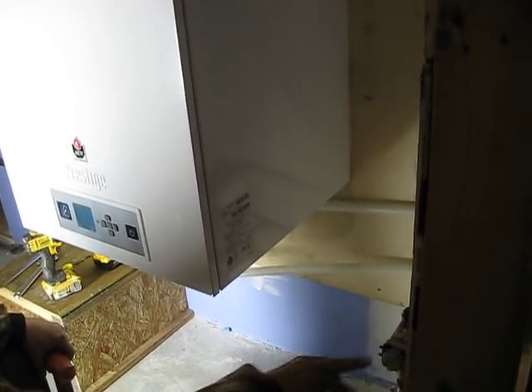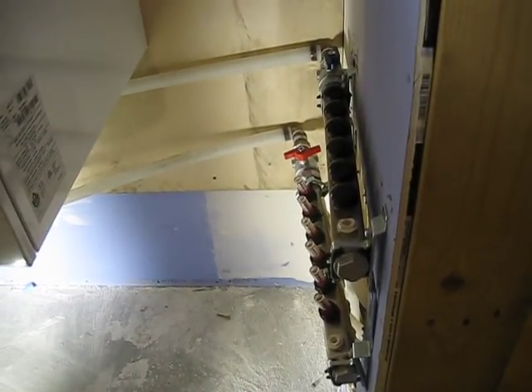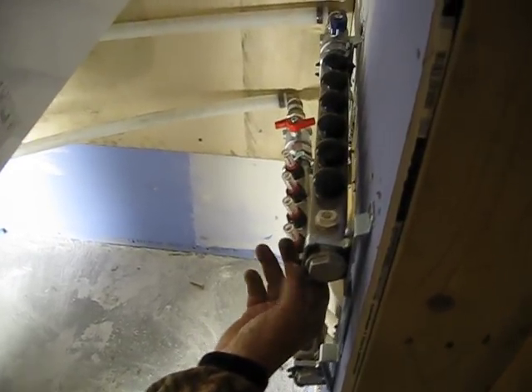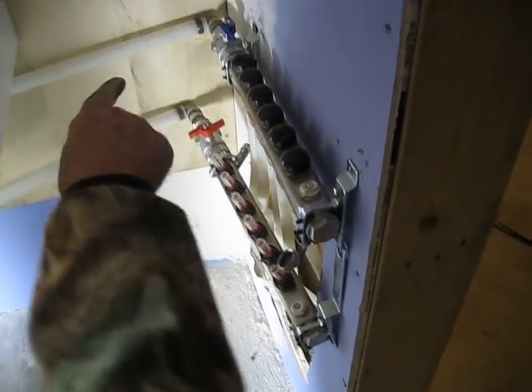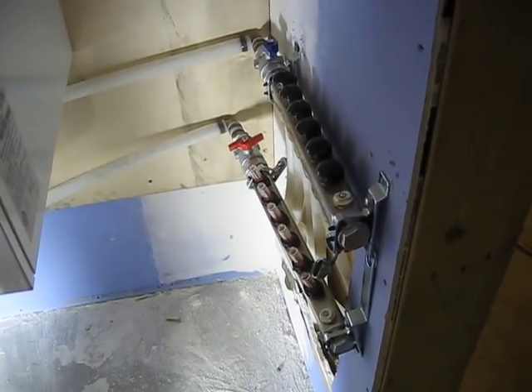Toasty. You got to get the propane guy up here. Okay. You got to get the water hooked to this thing. We got to get this up. We got to make sure that this doesn't have a leak in it. Okay. Now, this is a way we can check that. We can put pressure here. We can close those two valves and put pressure and determine that none of this leaks. And then we got to come back here to determine none of this leaks.